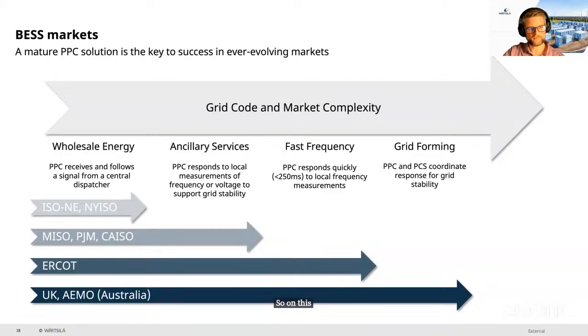On this slide, I'm showing a sliding scale of complexity for grid code and markets. If we start from the left side, we have large stable grids with firm baseload power that may only need a BESS to participate in a wholesale energy market, following a signal from a central dispatch without doing too much extra processing. The next level of complexity involves providing ancillary services. Primarily, those are frequency or voltage support, and those would require the PPC to react to a local measurement of grid conditions. Moving further to the right, we get into fast frequency response, which is typically 250 milliseconds or so, and grid forming capabilities, which include virtual inertia and short circuit contribution.